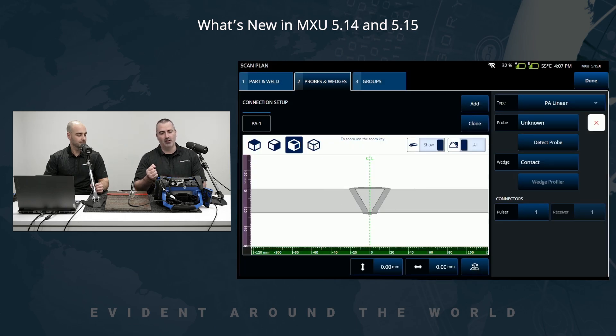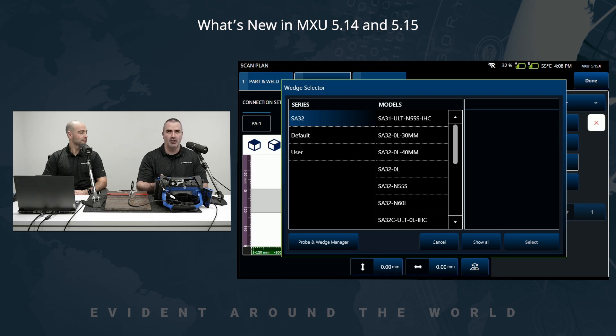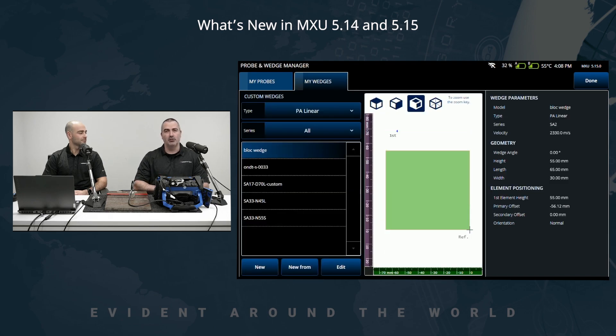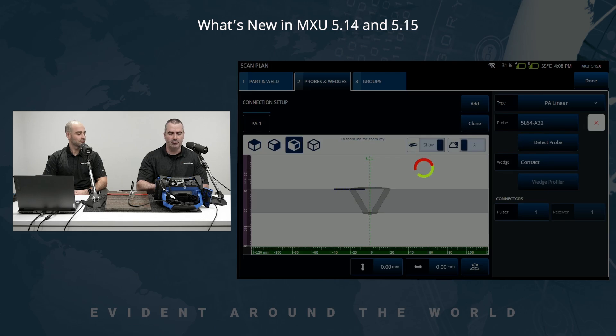The first feature on the list is the auto-detection of the phased array probe. For those familiar with the MX2, detection used to happen on the probe connection, which came with its benefits and drawbacks — mainly multiple misconnections. Now we have a dedicated button on the interface. As you press Detect Probe, it auto-populates the field with the probe information. We still have access to the wedge list as before, and new to this version is the ability to access the probe and wedge manager straight from the scan plan. We're using the standard 55-degree shear wave wedge, the SA32-N55S.